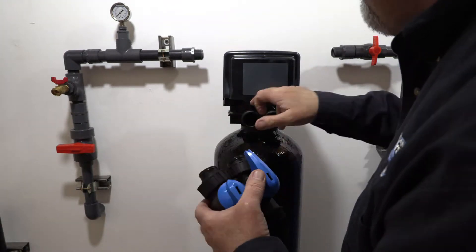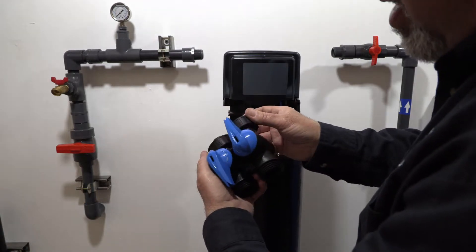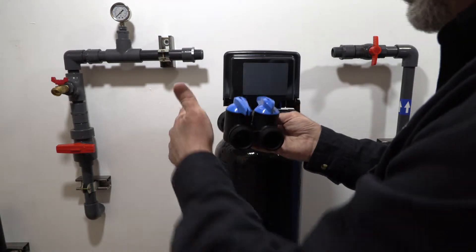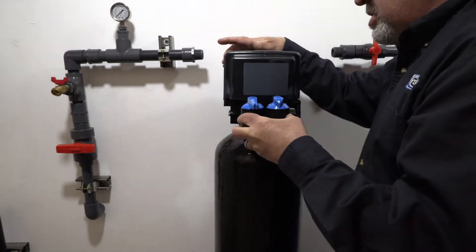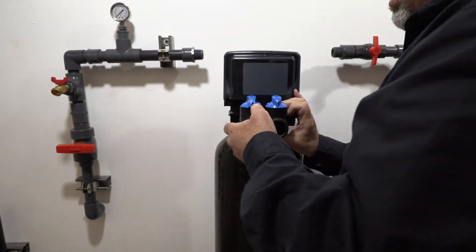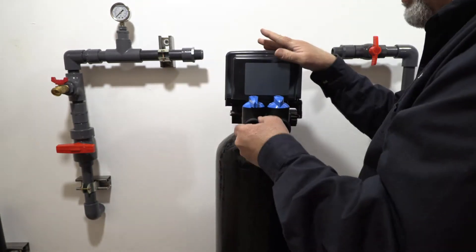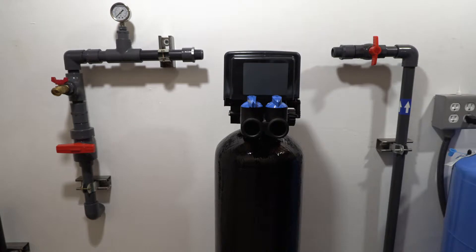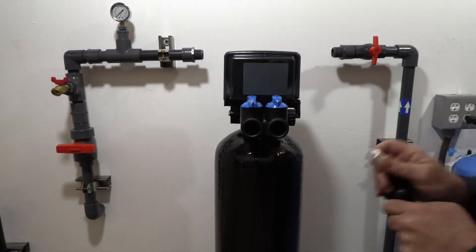On the back of the valve and on the bypass valve you can see there are arrows, so you want to match the arrows, the inlet to the outlet. This guy just slides in like this, and again just hand-tighten the fittings. The o-rings do the seal, so you don't need to worry about that.